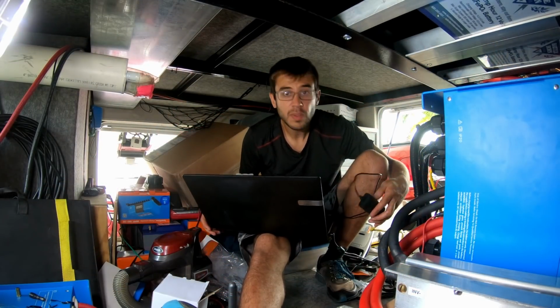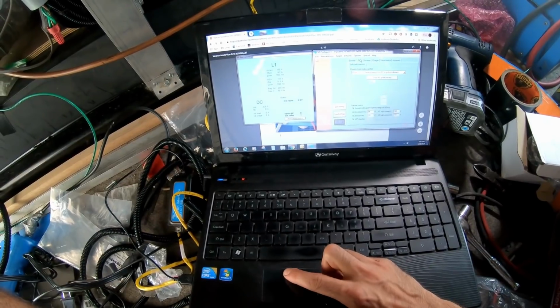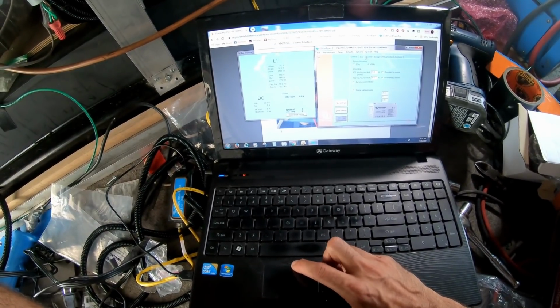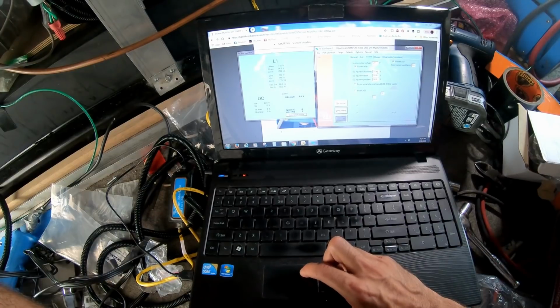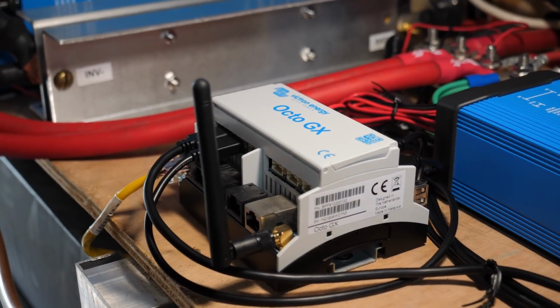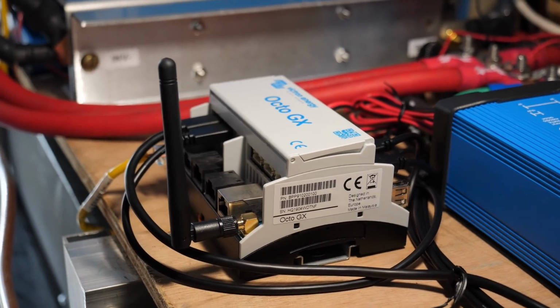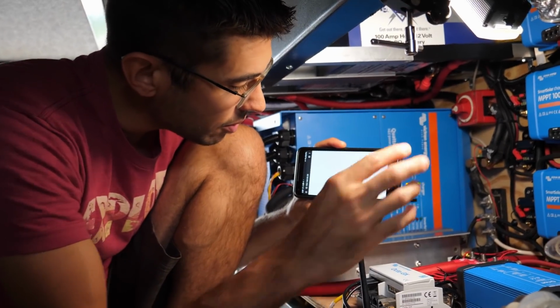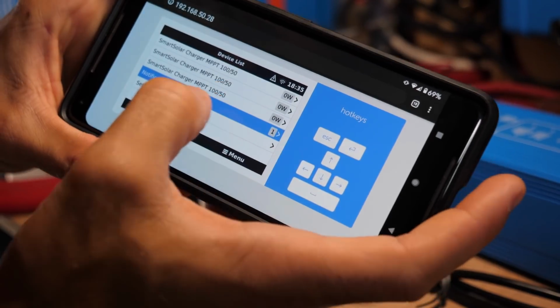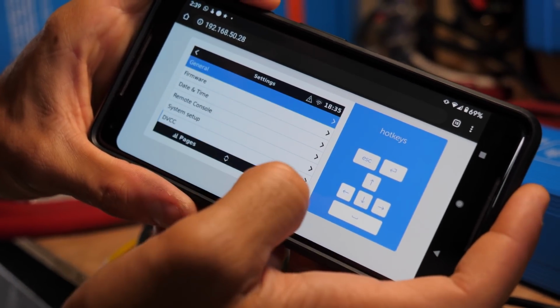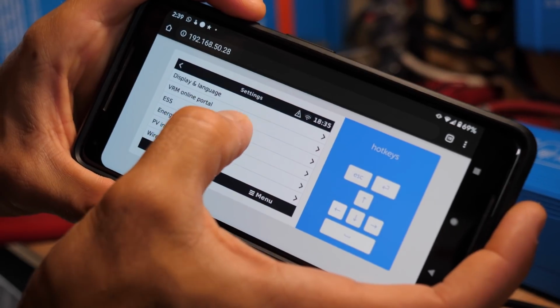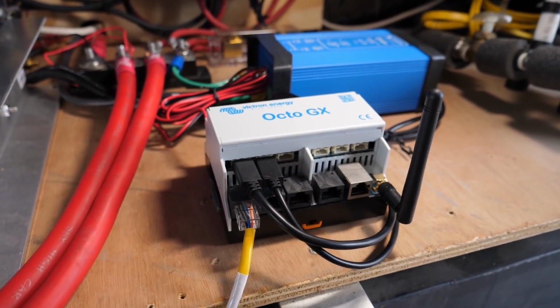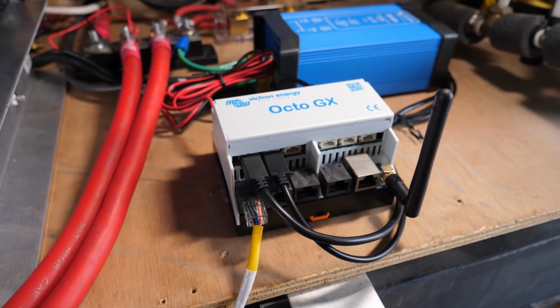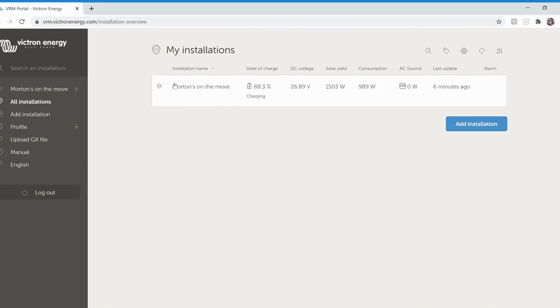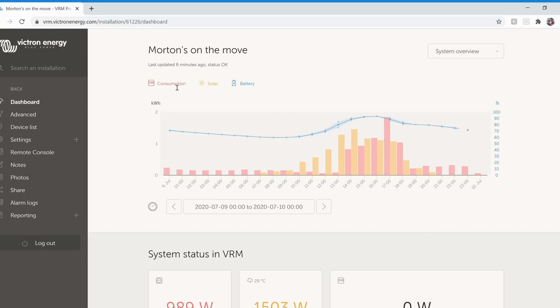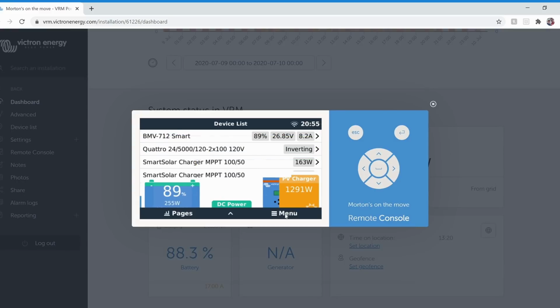Programming the inverter was done with a converter and special Victron software. The inverter needs to be programmed to the proper charging characteristics for the batteries it's connected to. After being programmed, it was hooked up to the Octo GX unit and then brought online. This is done using a Victron app on a mobile device to connect to the GX's Wi-Fi network, then run a special remote access control panel on the phone. From here, we connected it to our local Wi-Fi network so it could be accessed and upload its data to the Victron VRM portal, where we can monitor and control the system from anywhere in the world.